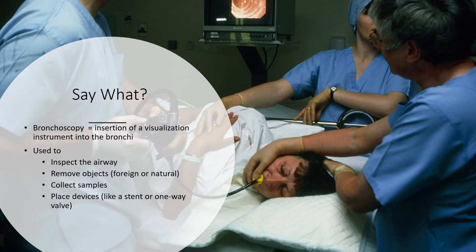In this picture, you're going to see a person lying on their left side dependent with a bite block in place. That bite block prevents patients from biting down on the scope. This is a flexible scope, and these are very, very expensive and very sensitive — there's a bunch of fiber optics inside. If the patient bites down without a bite block, it's thousands of dollars to replace those fiber optics. If you see little black dots on the screen when looking through the scope, that means broken fibers — it's been damaged or pinched. Scopes can also be used for cryotherapy and other procedures.